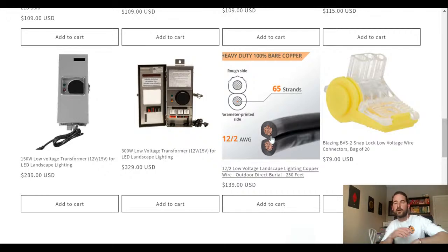There's going to be very rare circumstances. In all the years that I've been doing this, for the last 10 years, there's only one case where I had to use some 10 gauge wire, and it wasn't for the whole system. It was just because they had a driveway that was, whatever it was, 1,000 feet long. So we ran 10 gauge up until we got to those lights, and then we did 12-2 wire.